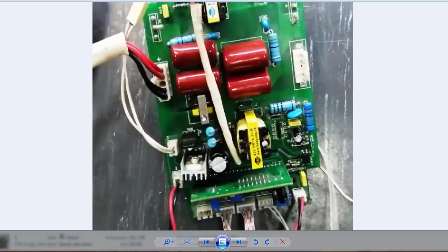The second thing, in our discussion of the IGBT driver module and power module, I discussed the filter inductor. It is actually a peak current detector. In our last video, if you remember, I discussed that all current flows from this inductor. So basically it's not an inductor, it's one side coil, the mainline coil, just a jumper, but in the same core there is a winding that transduces the amount of current flowing in the IGBT power section. If there is a short circuit or overcurrent condition, this peak detector will send a signal to the control board.